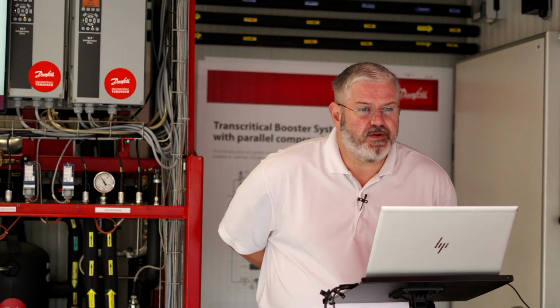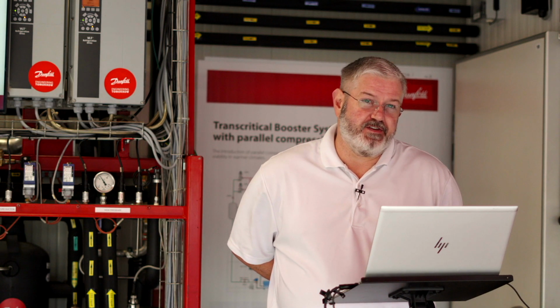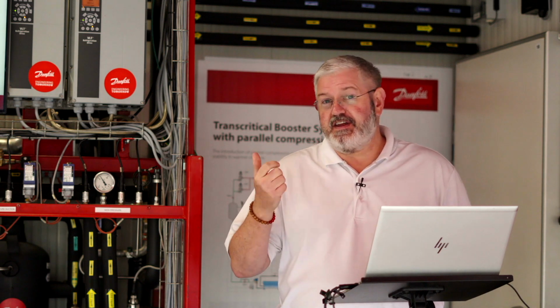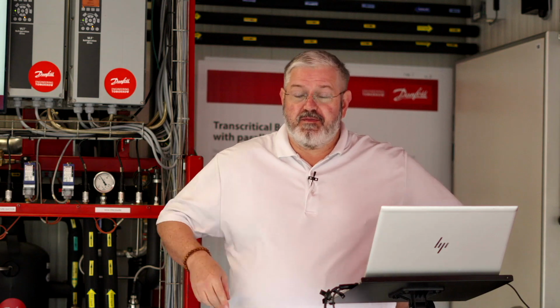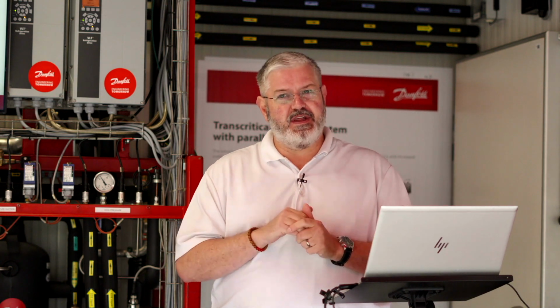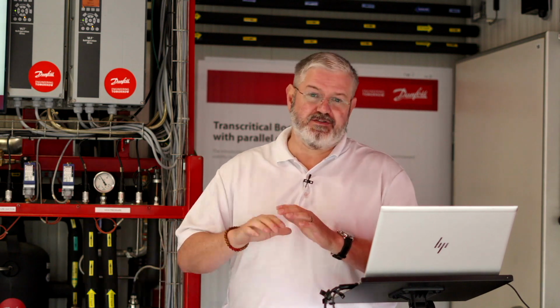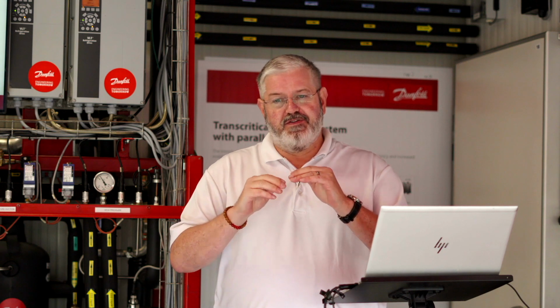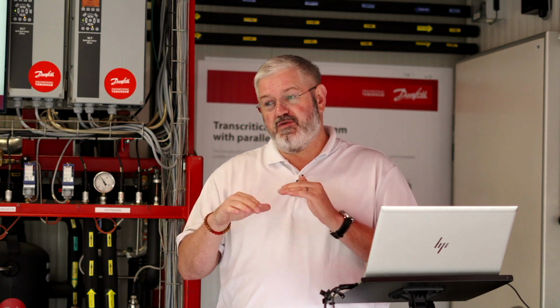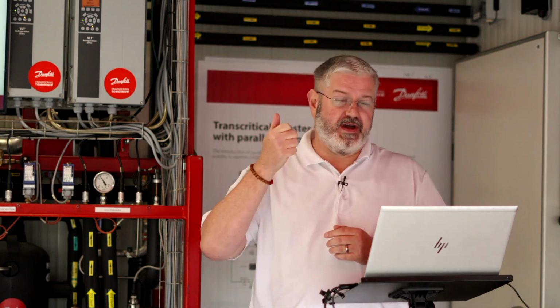And then is 744 considered refrigerant grade CO2? So 744 is actually the identifier for the refrigerant itself. Carbon dioxide, its identifier is R744. I'm glad someone asked this because there are different grades. I believe the minimum grade that you would use, and this is based on compressor manufacturers and valve manufacturers across the board, is what they call Coleman grade. So you want a minimum of Coleman grade quality in the CO2, and it's the percentage. They'll refine it and extract it. You might get lesser percentages for something like cleaning vegetables in an industrial application. But for refrigeration systems, you don't want to have any non-condensables. You're going to want Coleman grade or better.